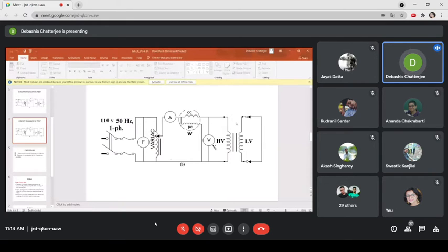The reason is, if you short circuit a transformer, as I was talking earlier, the current mainly flows through the leakage reactance path, and the load side is short circuit. That means if you apply a rated voltage and the series parameters are very small in magnitude, a large current is going to flow. So naturally you cannot apply rated voltage here.